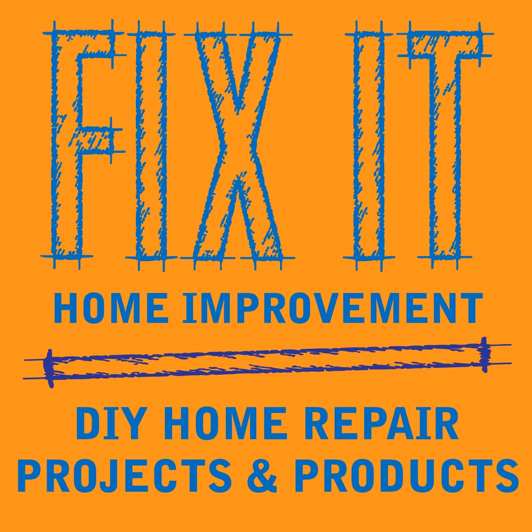Right. If the water keeps leaking after you've tested it, you need to change it. You never want to plug or cap a temperature and pressure relief valve. It could cause the water heater to explode. And the temperature and pressure relief valve should be changed every 5 years, even if it's testing okay. You should mark the side of your water heater with the date with a magic marker and just change it every 5 years.